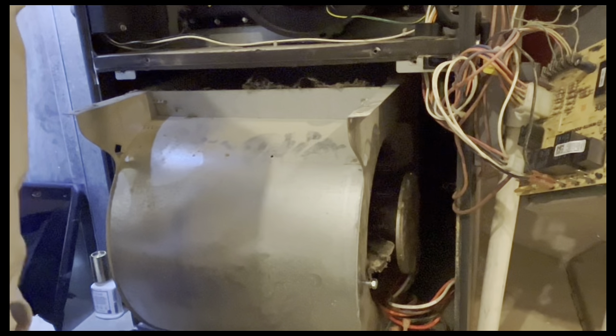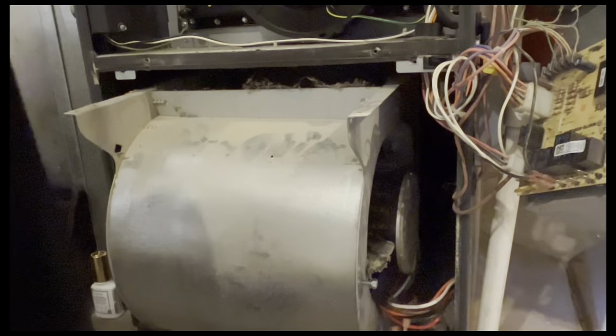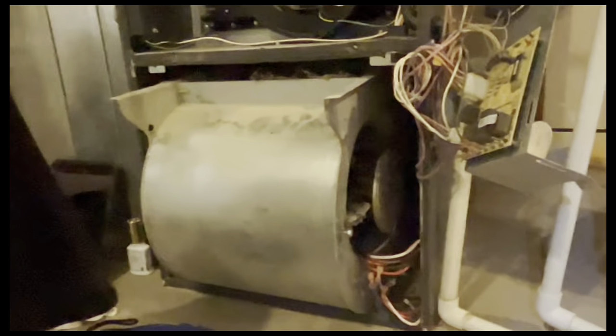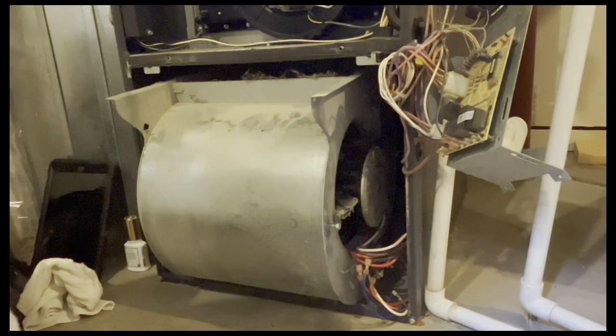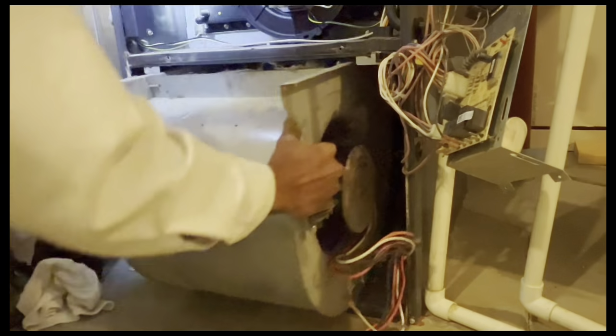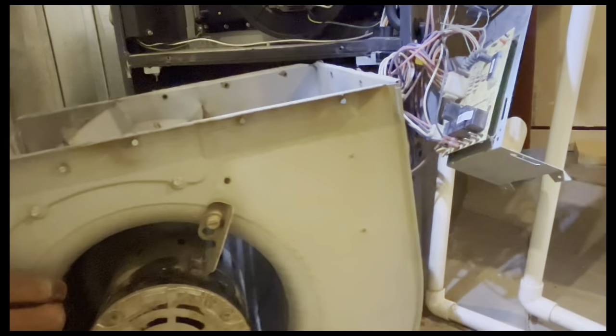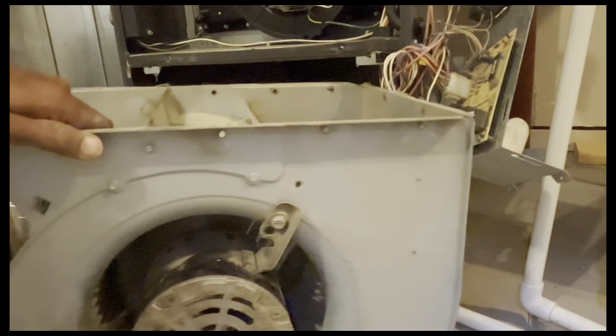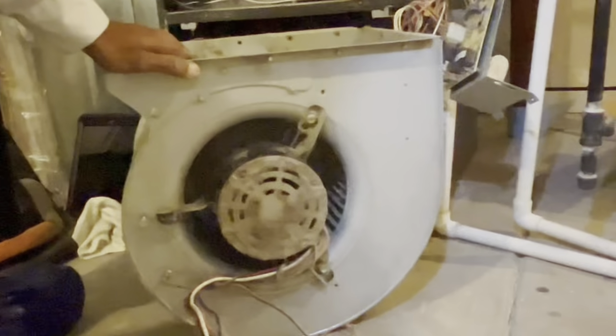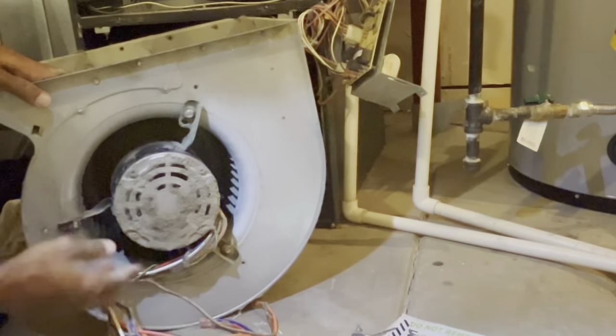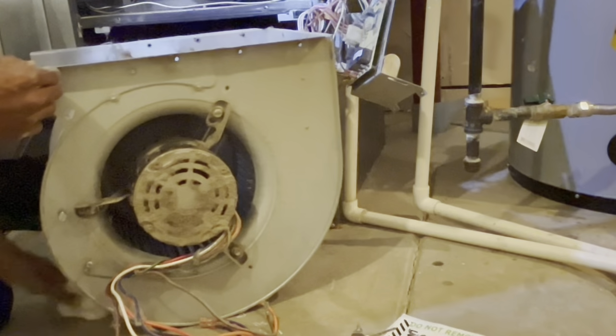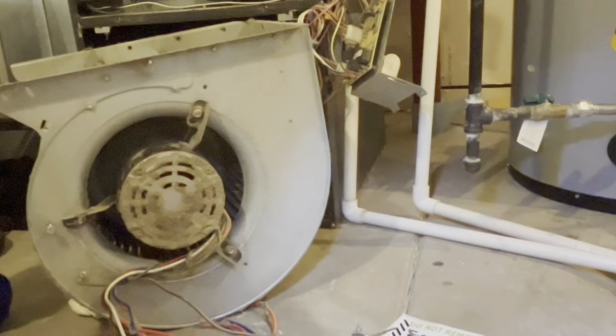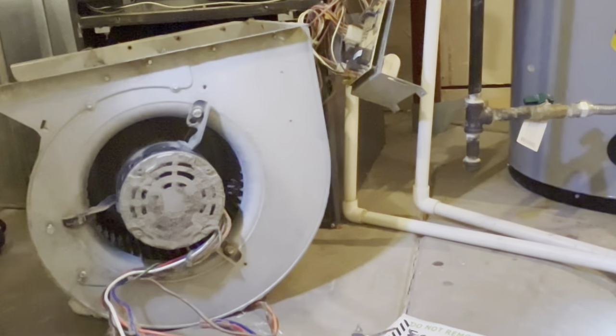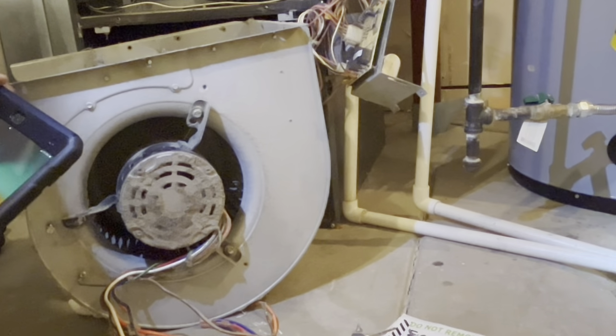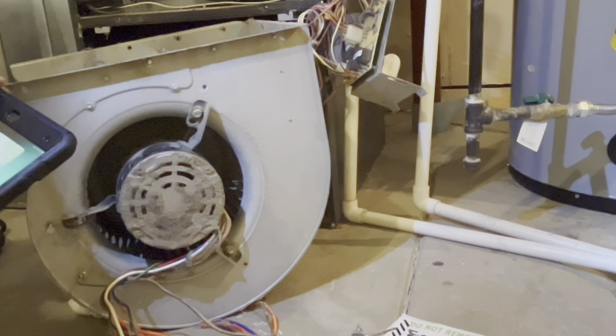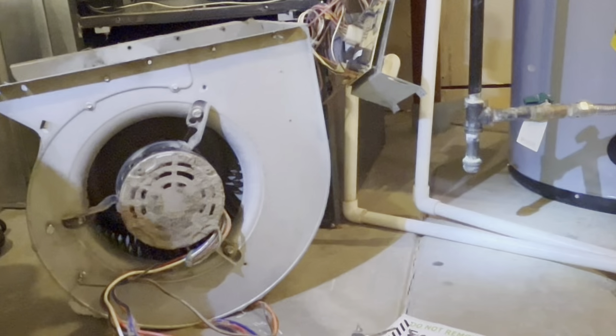And when dirt and debris gets onto these major components like this blower motor, it can cause the seal to fail. It's a sealed motor, and basically it has a certain amount of oil in it, and whenever that seal breaks and it starts leaking oil, then it has a lot of shaft play, and then you have a potential for a breakdown. You can see how much dirt and debris is on that motor. I mean, it was caked on there. And just to think about, if it's running constantly, it's going to be running hotter because it can't breathe. The air cannot get to it where it needs to cool it off. So it's going to run hotter, and if it runs too hot, then it's going to have a potential for a breakdown.